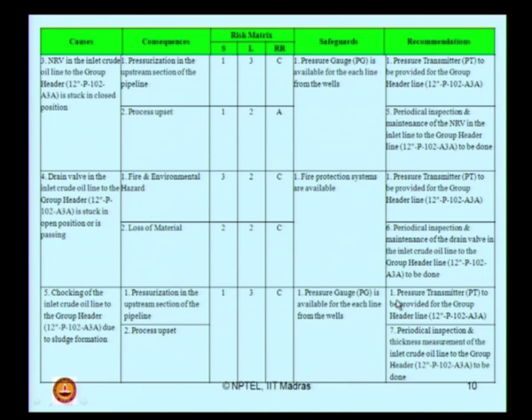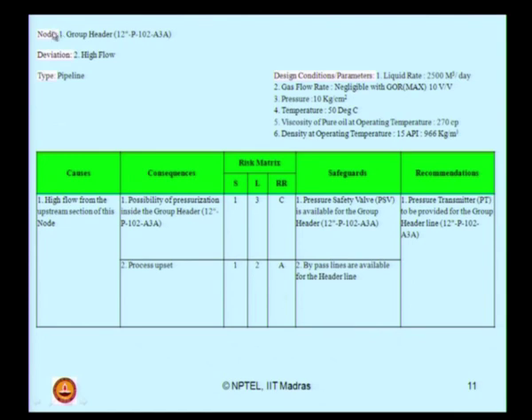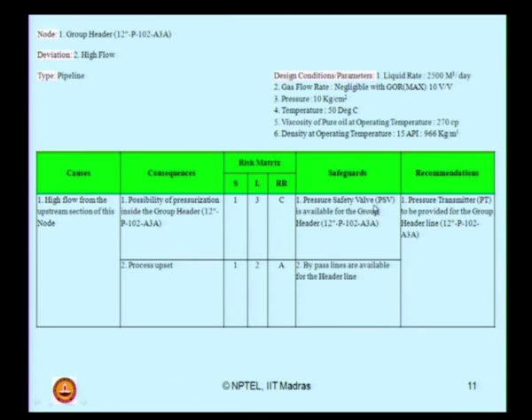For the same node, the second deviation is high flow — the previous deviation was low or no flow. The type is a pipeline and operating conditions remain the same. The cause can be high flow from the upstream section of this node, which can cause pressurization of the line. A pressure safety valve is already provided in the line, but we still recommend installing a pressure transmitter in the Group Header line. The recommendation number is carried forward in the same fashion from the previous deviation.